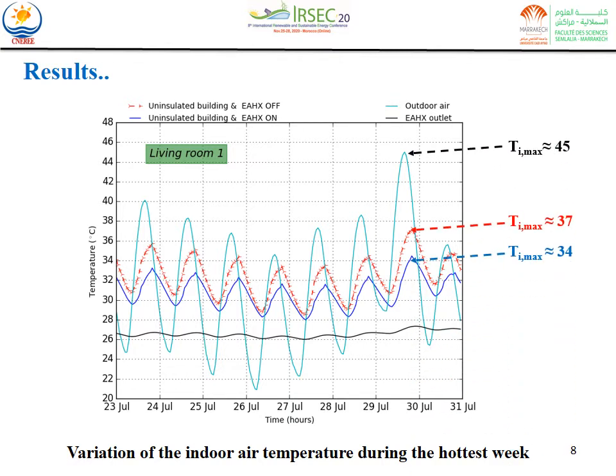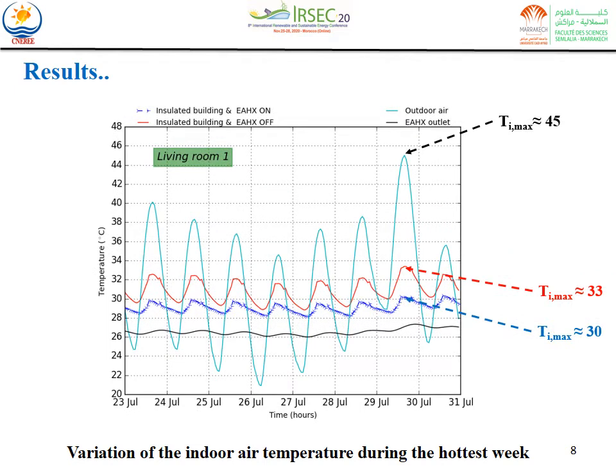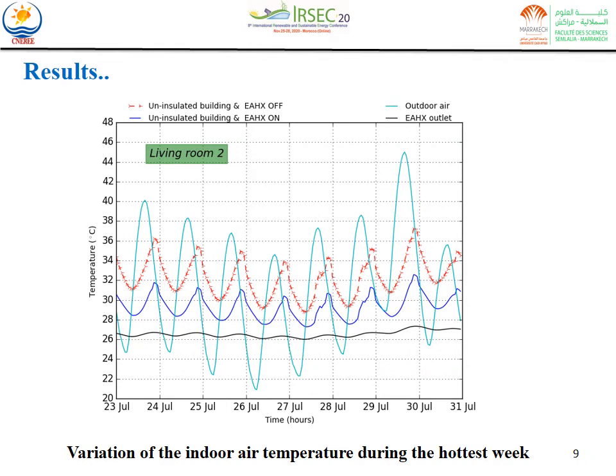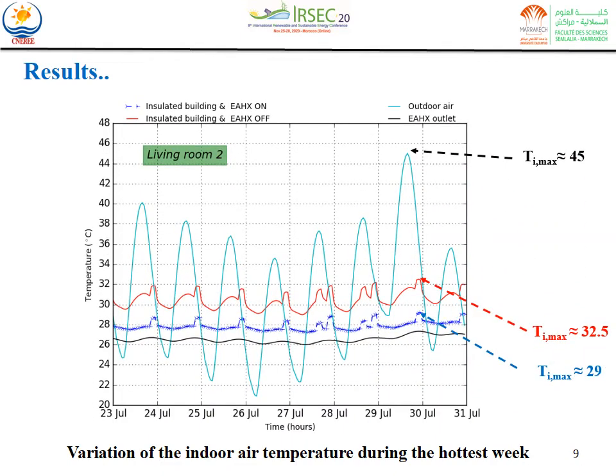In the case of the non-insulated building, the indoor temperature can reach a maximum of 37 and 34 degrees C respectively without and with the earth exchanger. And in the case of the insulated building, the indoor temperature can reach a maximum of 33 and 30 degrees C respectively without and with the earth exchanger. For the second zone, the indoor temperature can reach a maximum of 37 and 32.5 degrees C respectively without and with the earth exchanger. And in the case of the insulated building, the indoor temperature can reach a maximum of 32.5 and 29 degrees C respectively without and with the earth exchanger.